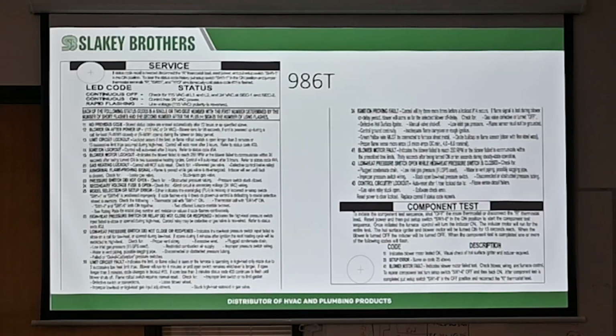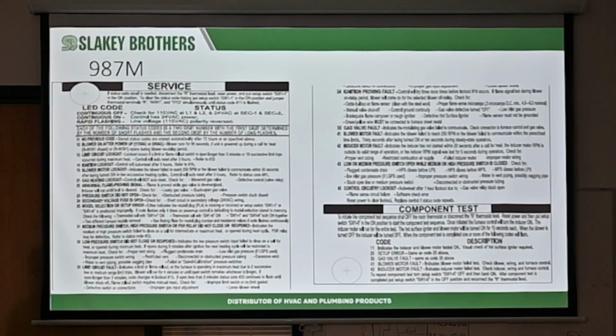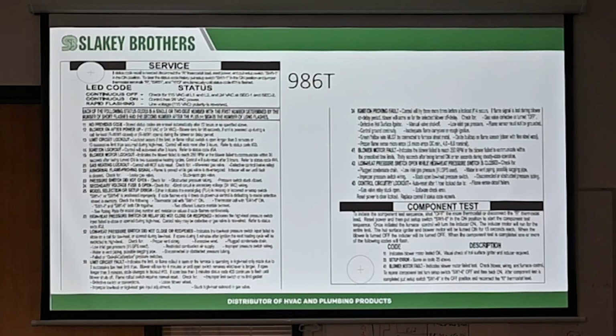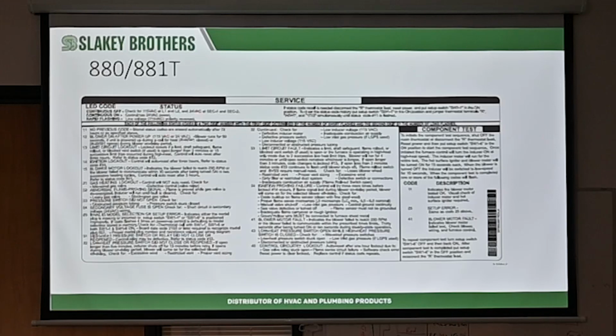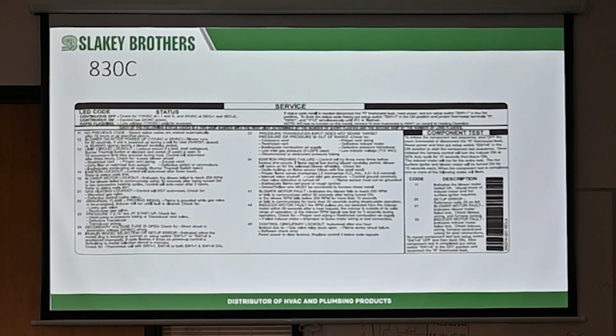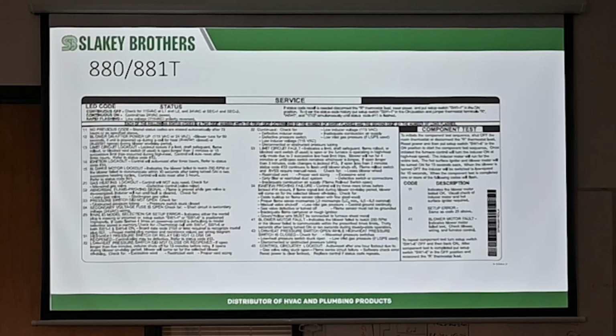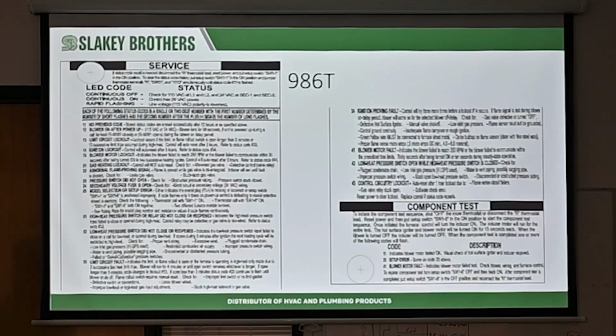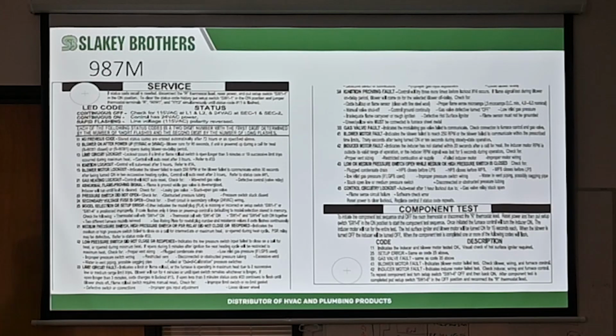Oh, by the way, notice how I gave you a manual for the 987. There is no manual. They didn't come up with a manual for 986. There's no manual for an 880 or even our 830. But here's the trick. Pretty much same blower motor. The 987, a major difference here is the ECM inducer motor. It is an ECM inducer motor because of that modulating furnace. The other ones are 2-stage. That's the only difference. So it's just going to be a lot easier to diagnose in regards to low fire rate or high fire rate for the inducer motor.